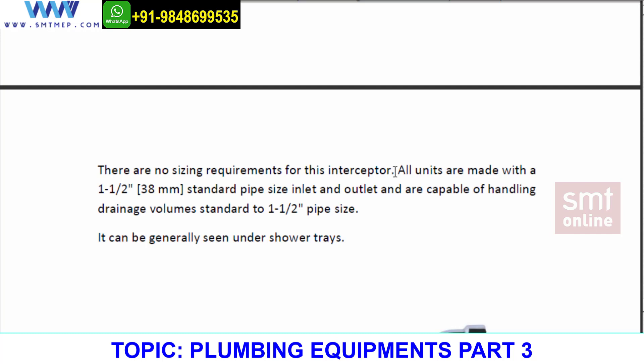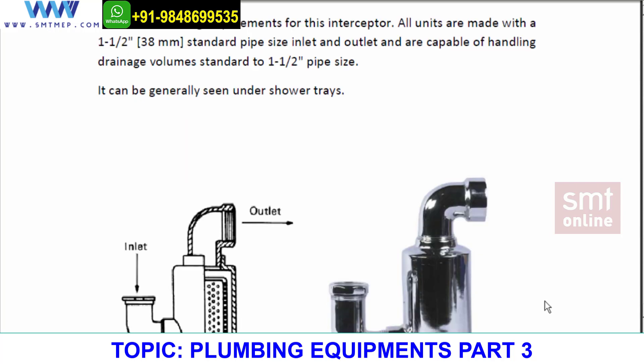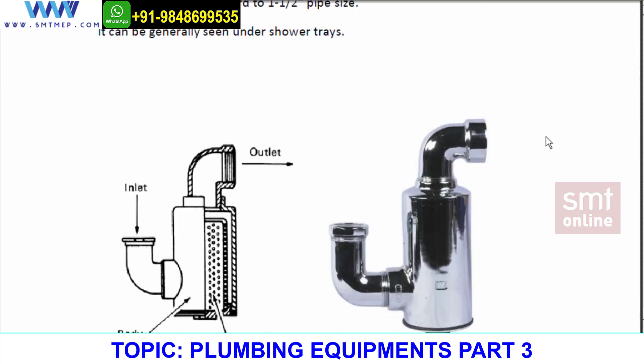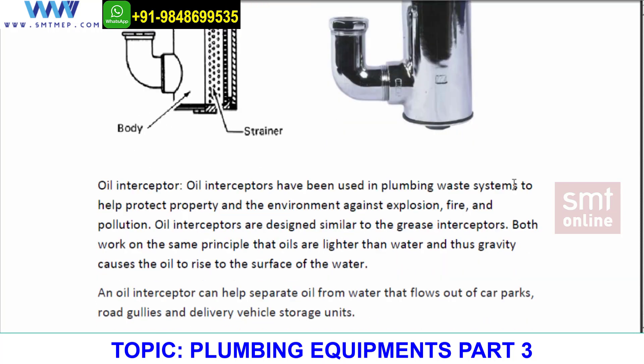There are no sizing requirements for the hair interceptor as there are for the grease interceptor. All units are made with a standard 1½ inch (40mm) pipe size, and both the inlet and outlet are capable of handling drainage volumes of a standard 1½ inch pipe. Hair interceptors are generally found under shower trays and are most commonly seen in Gulf country projects, especially in bathrooms used by ladies.